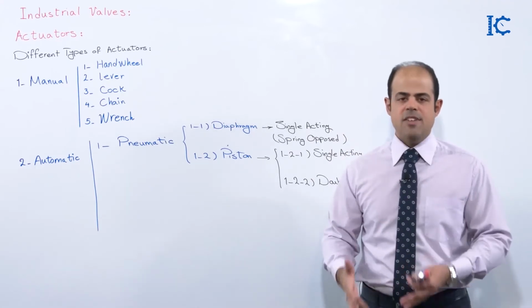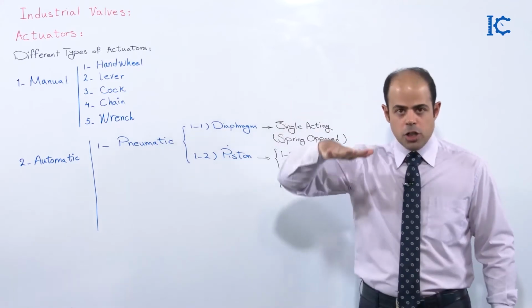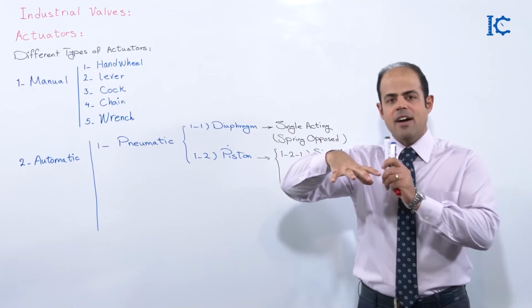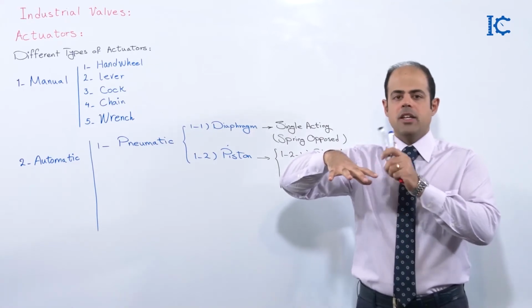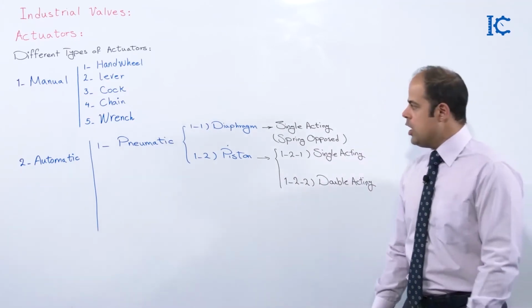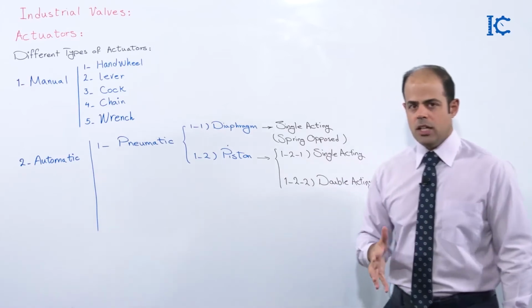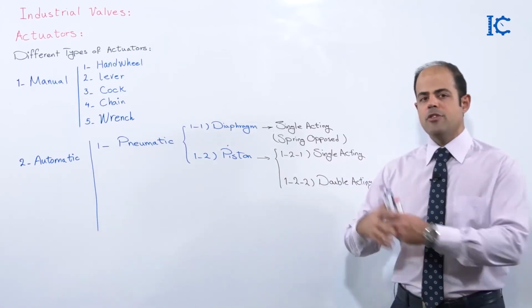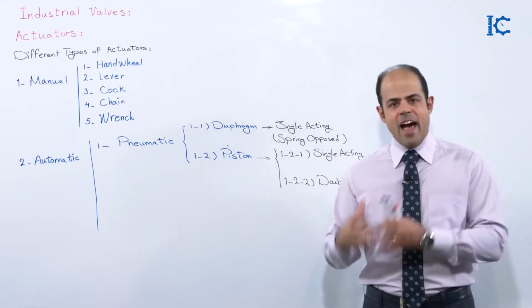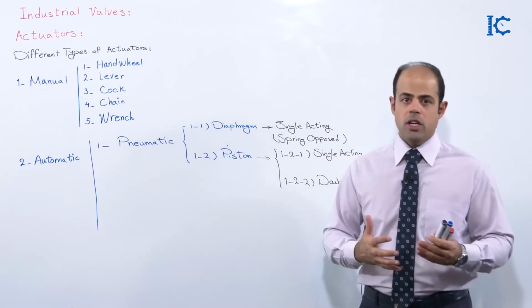It means that this valve is a fail to open valve. That's why it is air to close. Air is going to close the valve. The time that we do not have this air pressure, the valve is a fail to open one. As you can see, for the case of single acting, we have a spring. The time that we do not have any air, it makes the valve get back to the first position, whether it is open or closed.